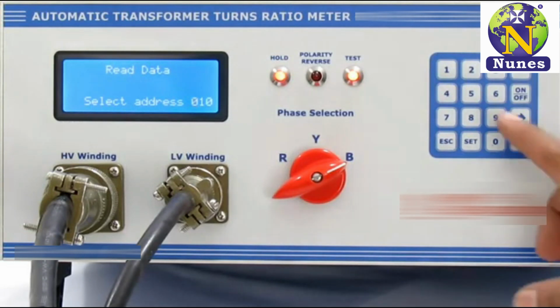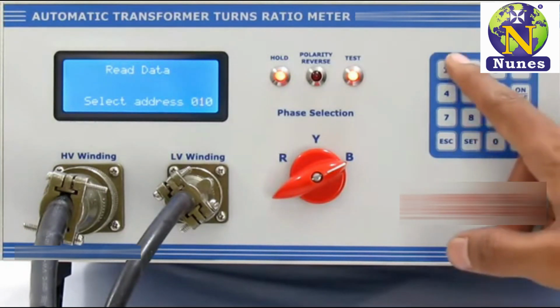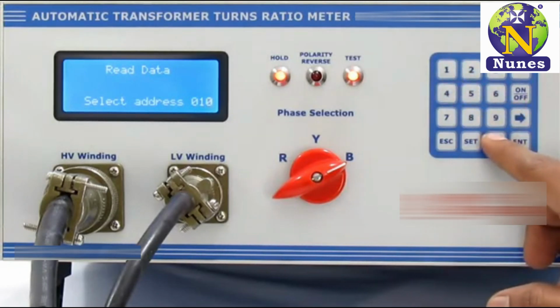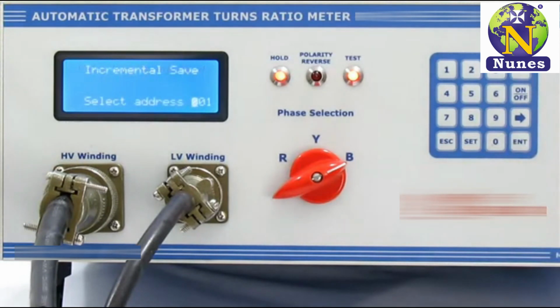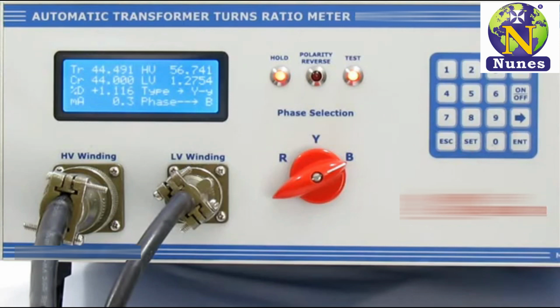Please select address as per your choice from 1 to 200 and press the enter button to see those results. You can see in the display that data has been read. Now press the escape key to exit. In this way, you can perform turns ratio measurement using this equipment.